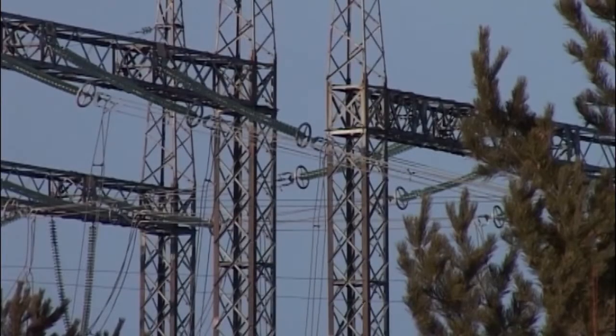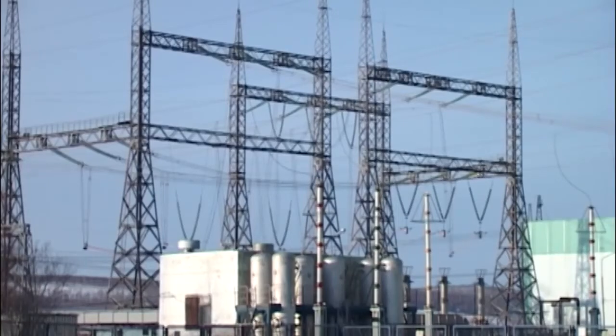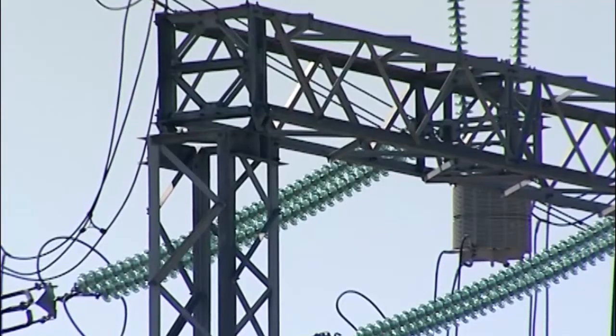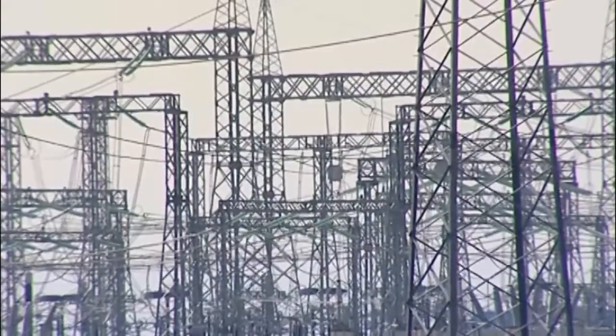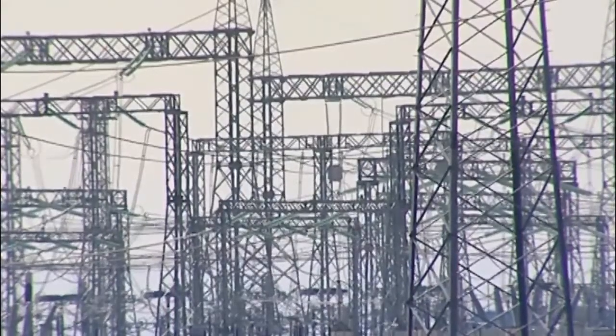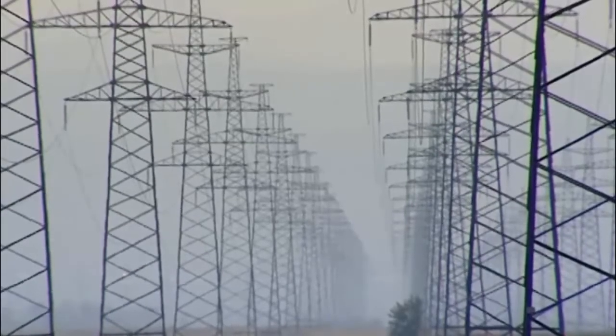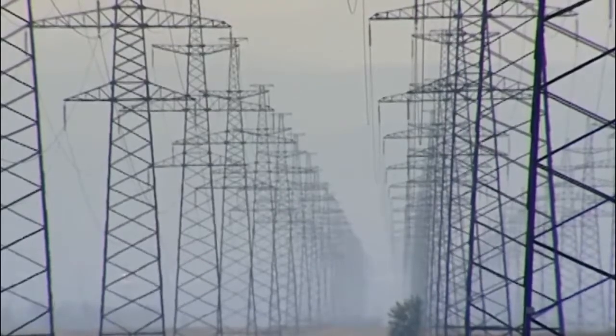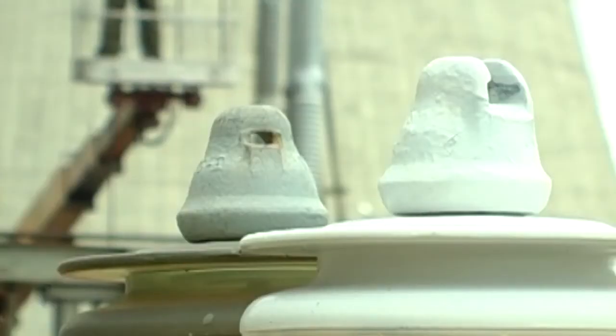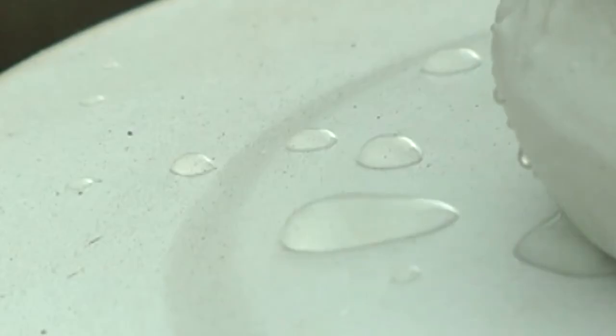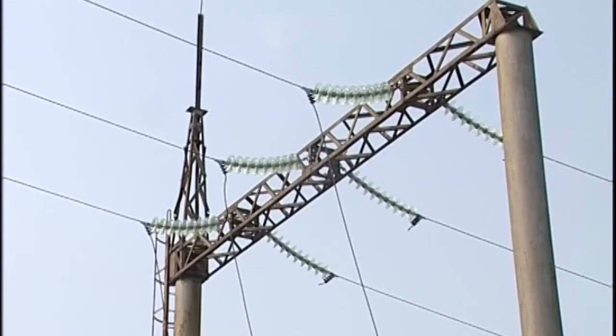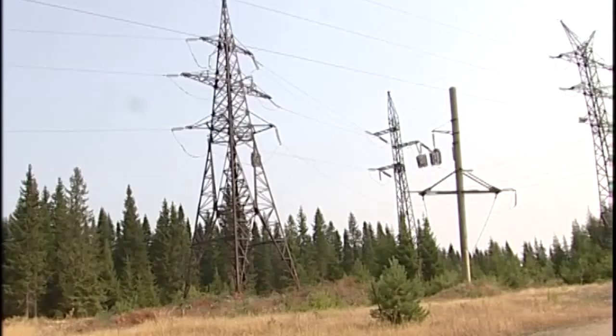One type of the contamination of insulators in atmosphere is emissions from industrial enterprises, which produce acrid reaction on the alkali glass surface, on which the glass is exposed to erosion. As time passed, the following processes occurred. NSDD and ESDD deposits lie over it and accumulate. Some of them are cleaned by rain and wind, whereas others aren't.